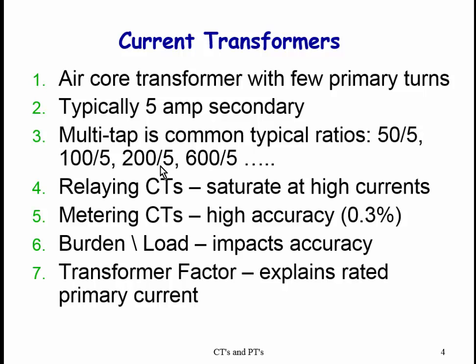But we use this to 5, and that's based on the old panel board meters being rated 0 to 5 amps. There's basically two different types. There's relaying CTs and metering CTs. Relaying CTs aren't quite so accurate, but they maintain a reasonable accuracy with a lot of current going through them. So during a fault situation, they still work reasonably well. In other words, they saturate at high currents. Metering CTs, they're more accurate because you're buying and selling power. However, during a fault situation, they're not quite as useful. So they're different designs, metering and relaying.